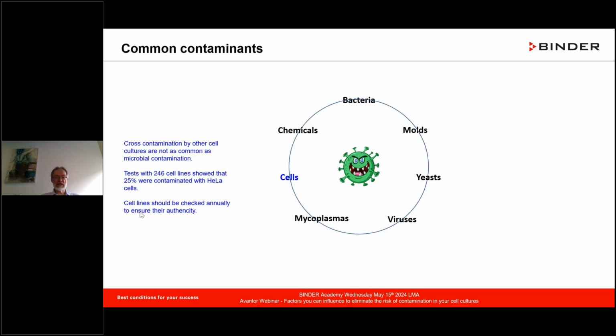Cell cross-contamination by other cultures is normally done outside of a CO2 incubator. Once in a while, we have inquiries saying, can it be that we have cross-contamination taking place inside of a CO2 incubator? That is not the case. Here we have a test, 246 cell lines were shown in a survey, and 25% were contaminated with HeLa cells. And there you always can expect some kind of adverse effects, making results questionable, and that is always a good idea to monitor closely the quality of your cell line and the contaminations you might have inside.